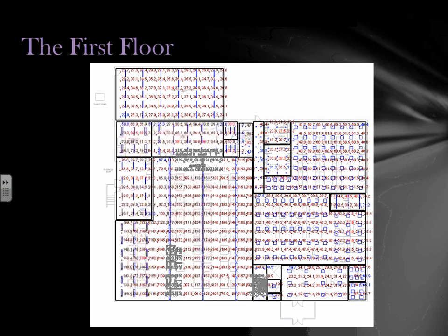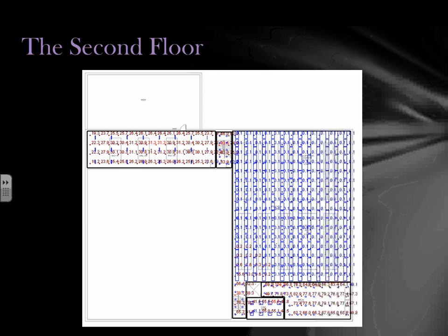That needed to have a range of foot-candles depending on where it was and what they were doing in that room. Things like the waiting rooms, you only need 20 foot-candles, but manufacturing, you needed to have 80. Second floor, sort of a similar thing. The break room is going to have 25 foot-candles, but the research lab is going to have to have 80. You need to be able to see what you're doing in much better detail.